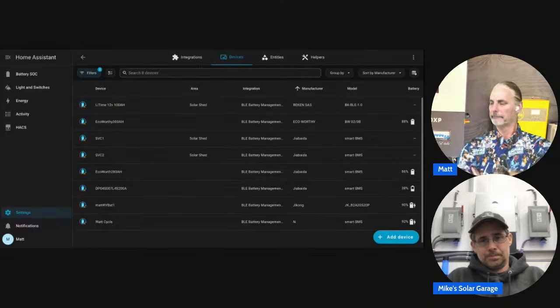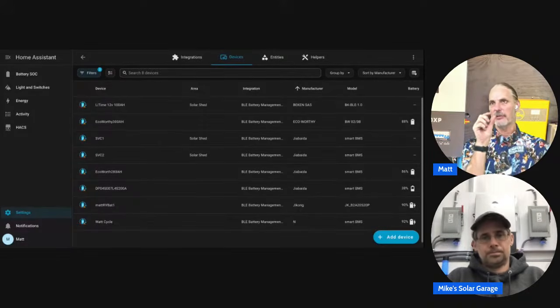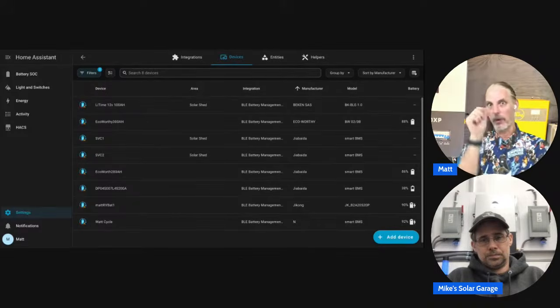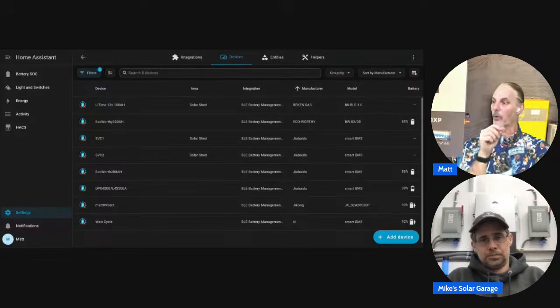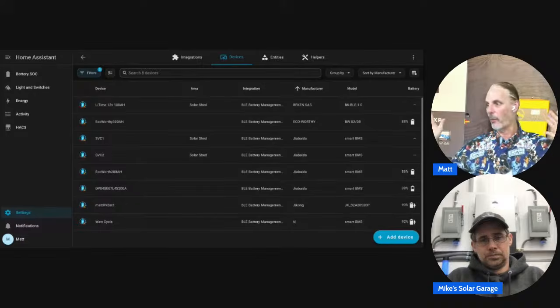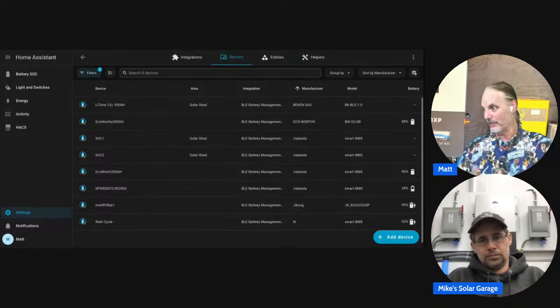Yeah, and that was one of the things that I liked about the DIY JKBMS, is that you could go in and set, instead of setting the pack voltage, you could set the cell voltage. So you could say, I want the battery, when the first cell hits 3.4, to start balancing. Because you can get to the point where your cells are so out of whack that it won't start balancing until you get up into 56.8 or so, because none of them ever make it there.